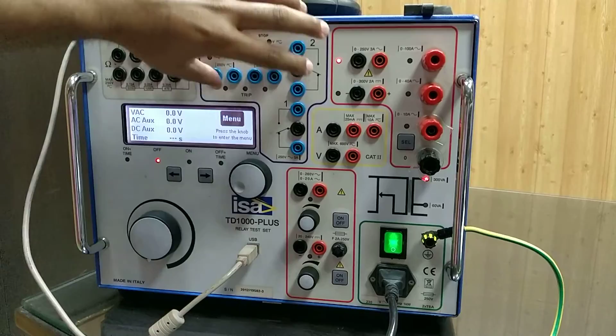It provides the digital input section as well as the digital output section, marked under the boundaries of the purple color. In this equipment, we have two digital inputs for measurement of timings, and we provide two digital outputs to simulate the circuit breaker status or any other conditions required as input to the relay.